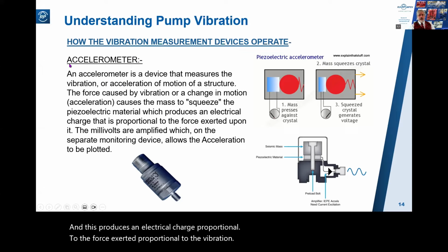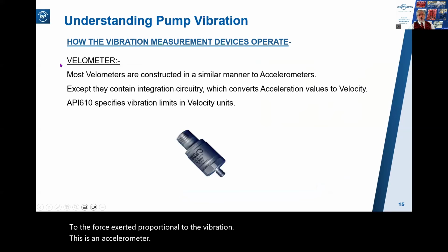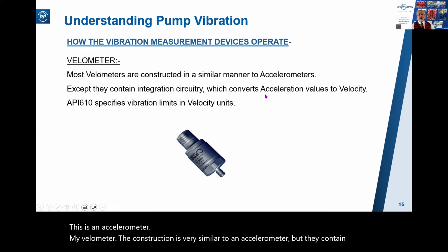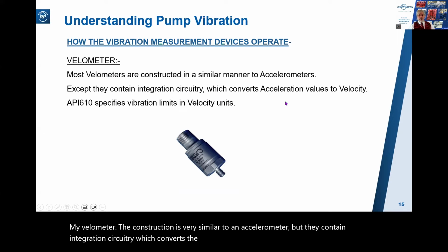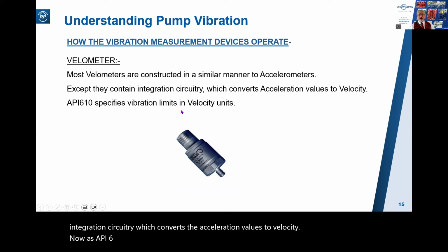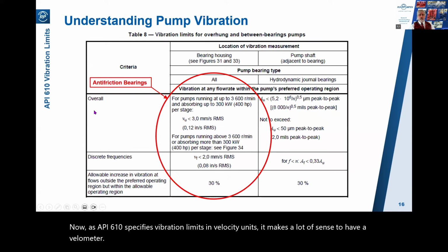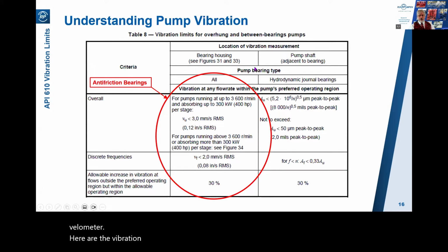This is an accelerometer. Now, a velometer, the construction is very similar to an accelerometer, but they contain integration circuitry, which converts the acceleration values to velocity. Now, as API 610 specifies vibration limits in velocity units, it makes a lot of sense to have a velometer. Here are the vibration limits of API 610 for anti-friction bearings, for ball bearings. It's table 8 in API 610.